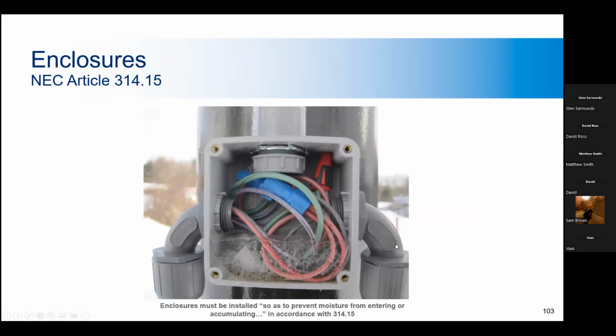So here's an interesting situation. Here we have an outdoor rated enclosure that was simply not properly installed. You can't really see that in this picture, but the conduit entry point isn't properly sealed at the top of this enclosure.